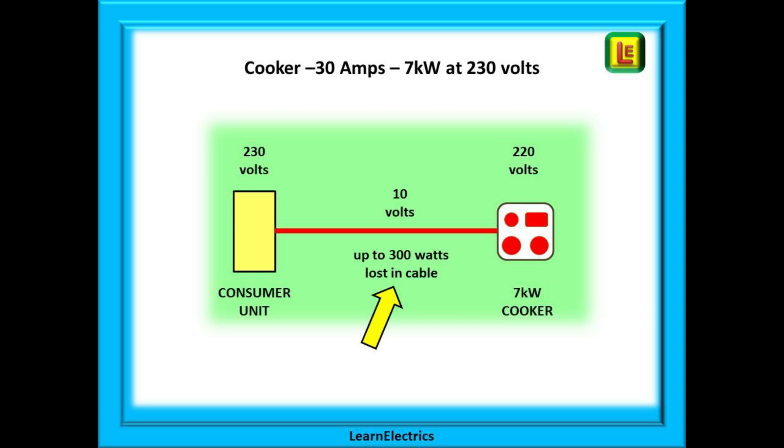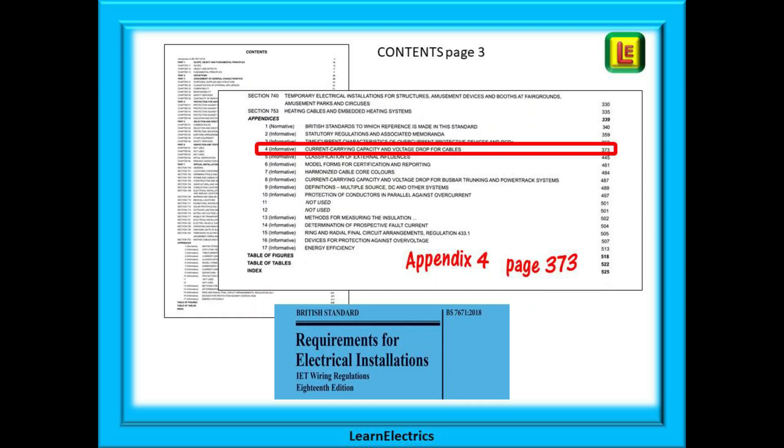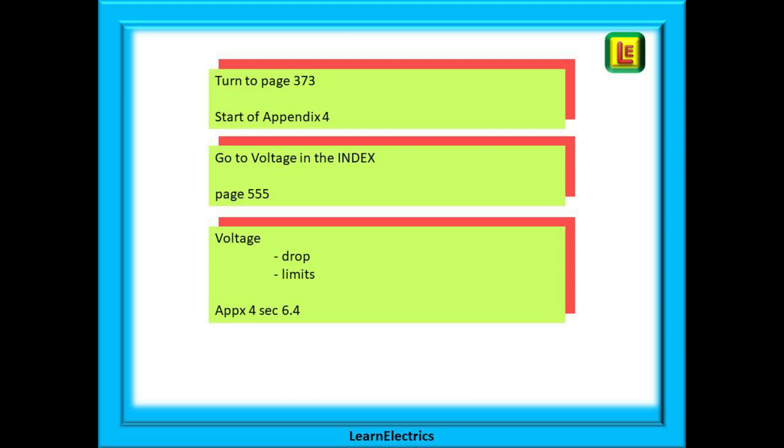We can start by looking in the wiring regulations and answering the first question: what is the maximum permitted voltage drop and where do we find the answer? If you've watched other videos from LearnElectrics, you will know that page three of the wiring regulations book is our go-to page. Always go to page three first. It is full of lots of information. Page three is the main contents page, and scanning down towards the bottom we find the appendices. Look at appendix four. It says current carrying capacity and voltage drop for cables. We can turn to page 373 as directed to the start of appendix four.